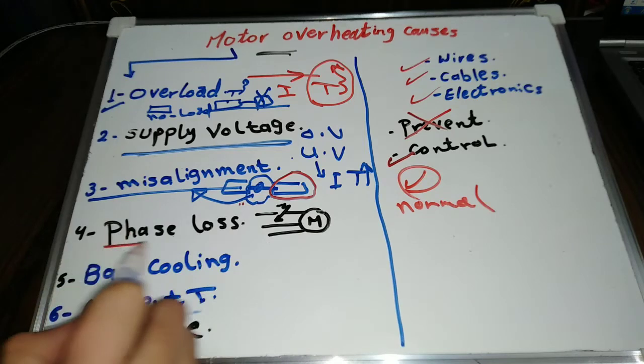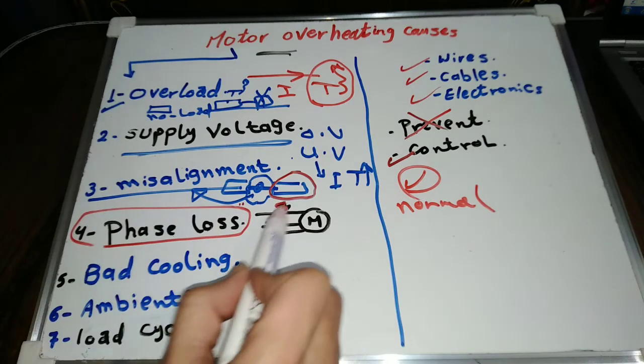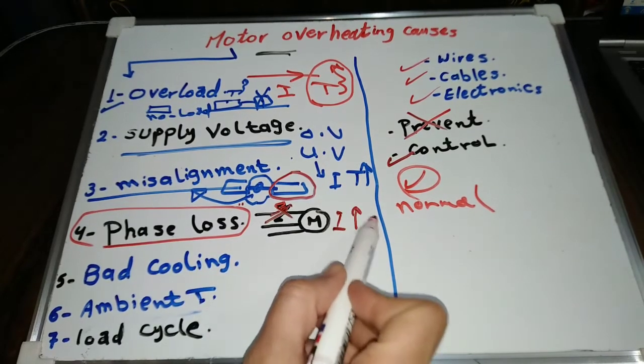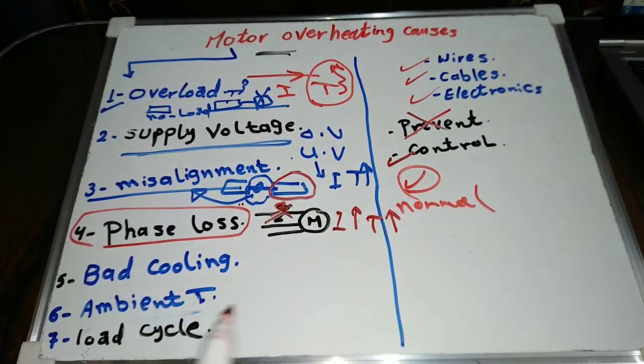Phase loss. If a three-phase motor works on two phases, we call this phase loss. It will draw higher current on the remaining two phases. Its temperature will rise and it will overheat.